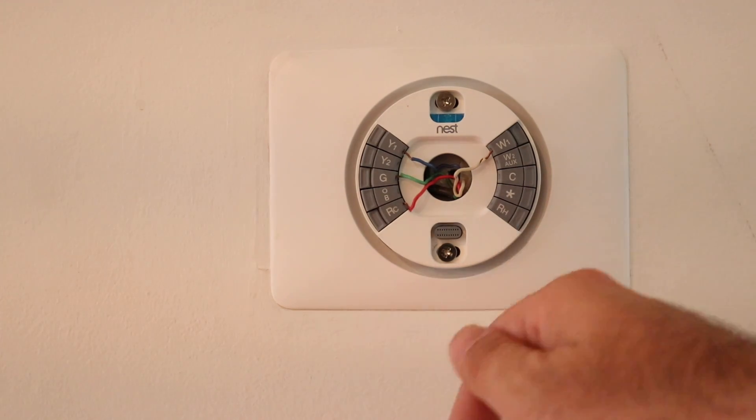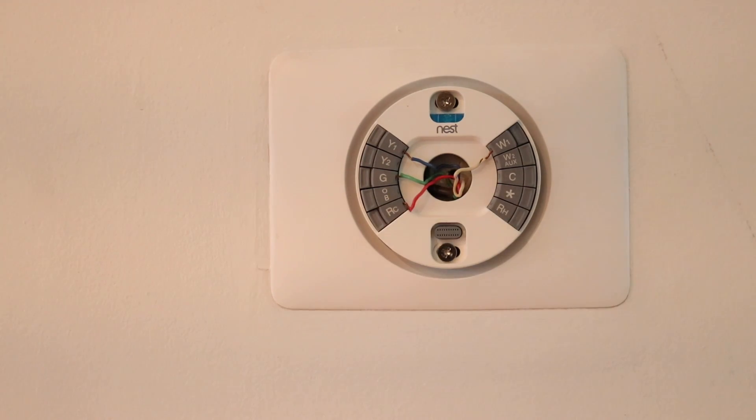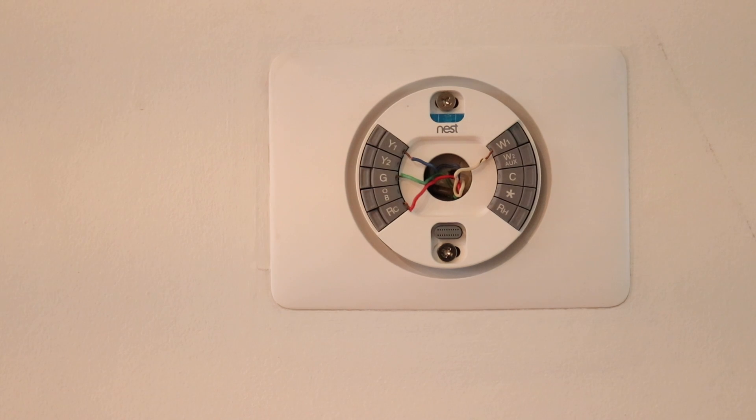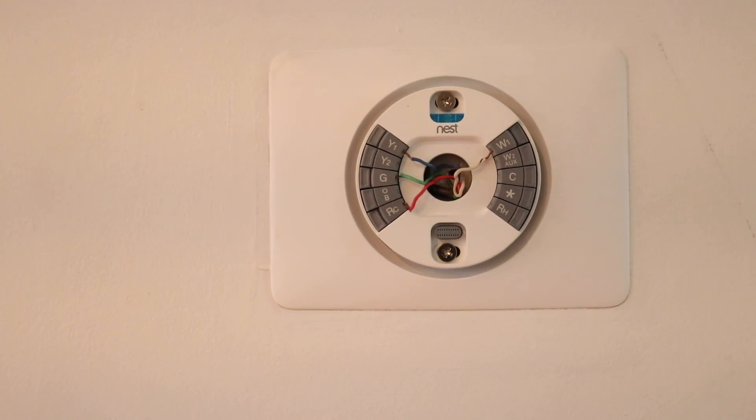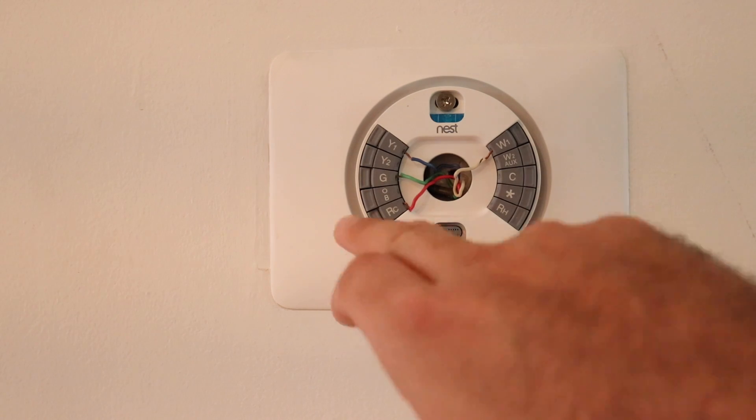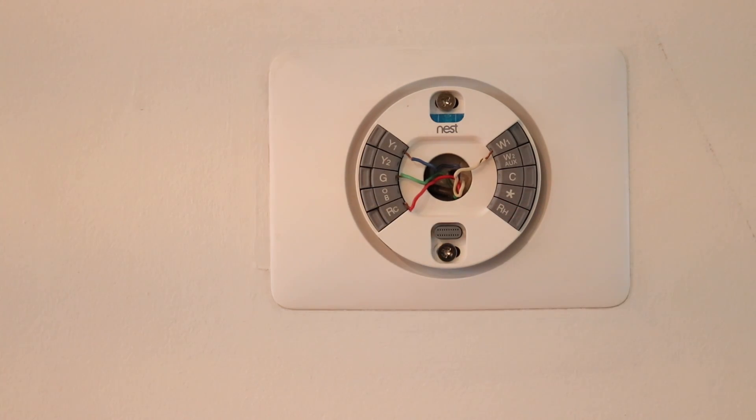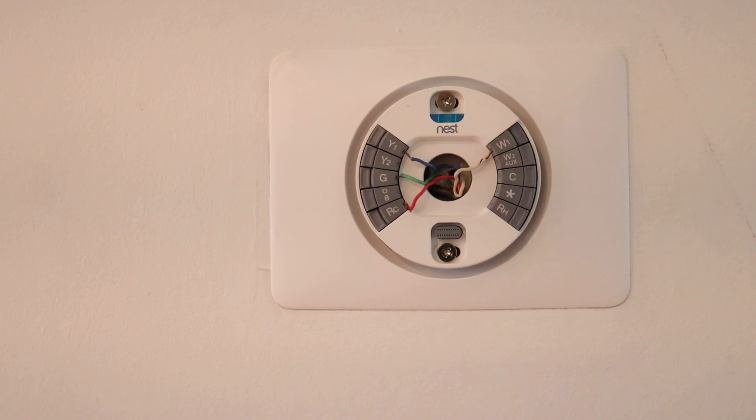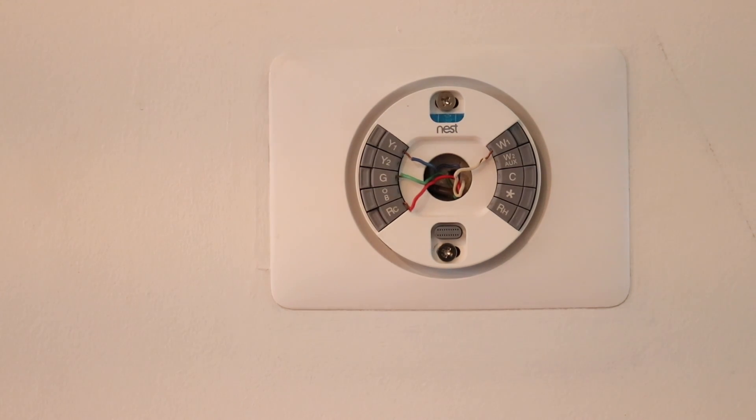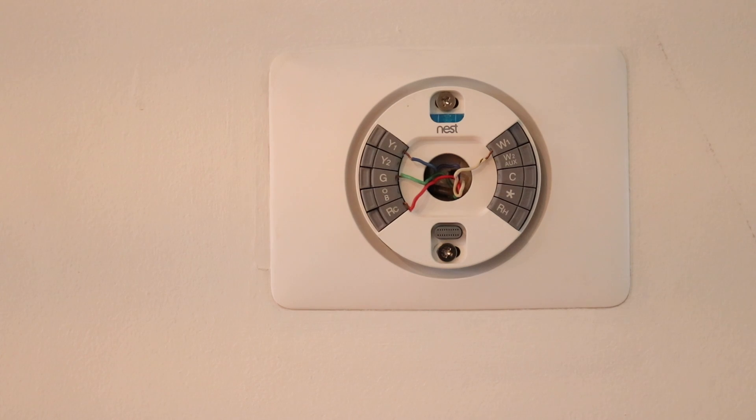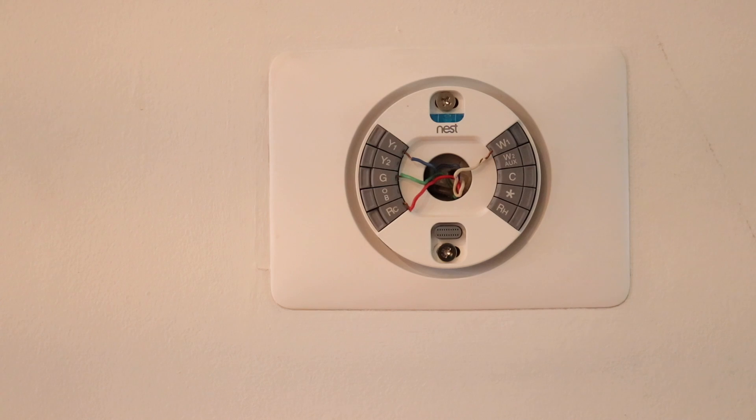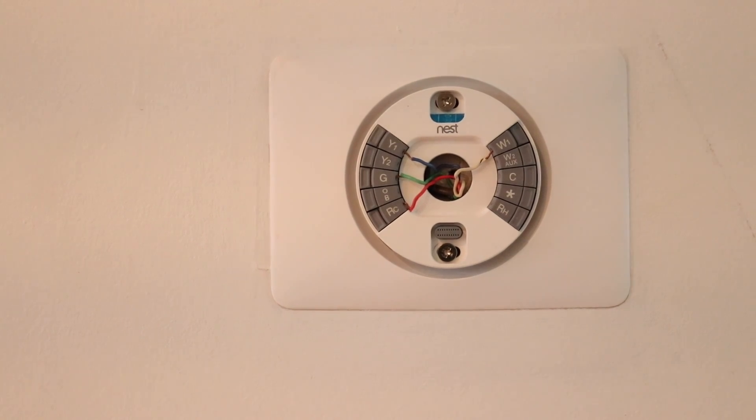The RH or RC wire, they're both used for power. If you have a dual fuel or dual power system, you might have an RC and an RH wire connected. Really, they do the same thing. You can put the red wire in either the RC or the RH. Technically, the RH is for heat power and the RC is for cooling power.